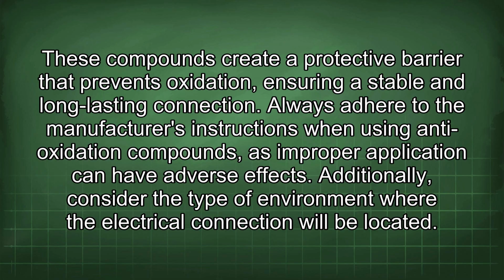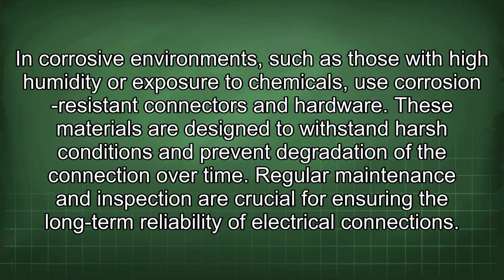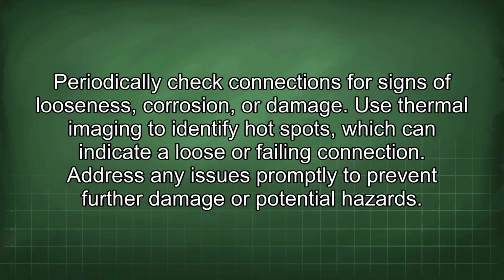Additionally, consider the type of environment where the electrical connection will be located. In corrosive environments, such as those with high humidity or exposure to chemicals, use corrosion-resistant connectors and hardware. These materials are designed to withstand harsh conditions and prevent degradation of the connection over time. Regular maintenance and inspection are crucial for ensuring the long-term reliability of electrical connections. Periodically check connections for signs of looseness, corrosion, or damage. Use thermal imaging to identify hot spots, which can indicate a loose or failing connection. Address any issues promptly to prevent further damage or potential hazards.